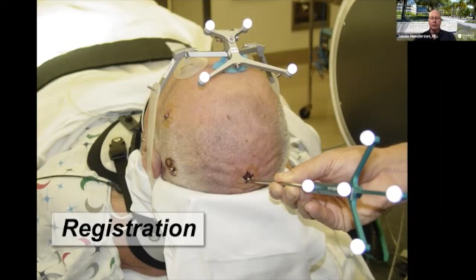So it's extremely accurate. And then you can see the device that's attached to the head with the strap, and that's a reference. The second part of this is that not only do we have to know where the head is in three-dimensional space, but we also have to know the relationship of those markers to the head. And the only way we can know that is to track the head. Otherwise, we just know where things are in the operating room, and that becomes useless if the head moves. Then the registration goes out the window. So that's why we have to have a reference attached directly to the head in some way. This is a device that we just place gently on the forehead with a strap that holds it in place while we do this initial registration step.